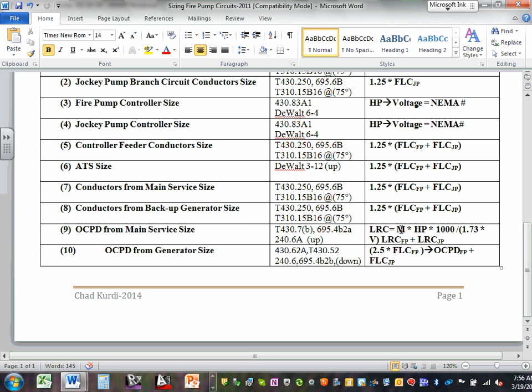You take M as the multiplier, which you're going to see in the NEC code book, from Table 430.7(B), multiplied by the horsepower, multiplied by 1,000, divided by the voltage and 1.73. And then you add the 2 locked rotor currents for the 2 systems. You add the 2 locked rotor currents for the 2 of them. This is from Table 430, for each one of them. You're going to see, we have an example coming in a second.